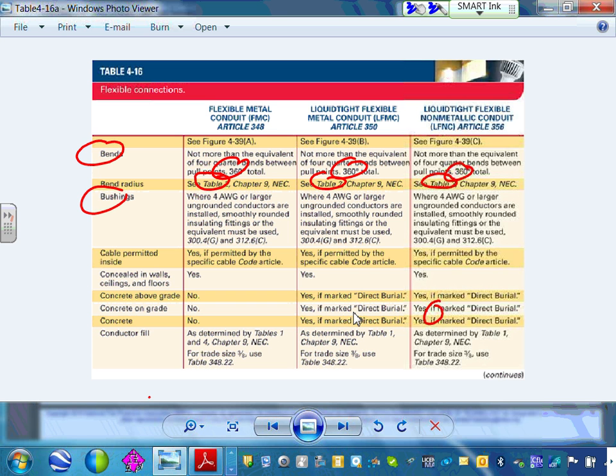Bushings. Everybody knows what a bushing is. The conductor, if it touches the conduit, will be damaged. So they have a little bushing that slides in to protect the conductor. When do you need that little plastic bushing pushed in? Almost all conduits, you need it if the conductor is size 4 or larger.